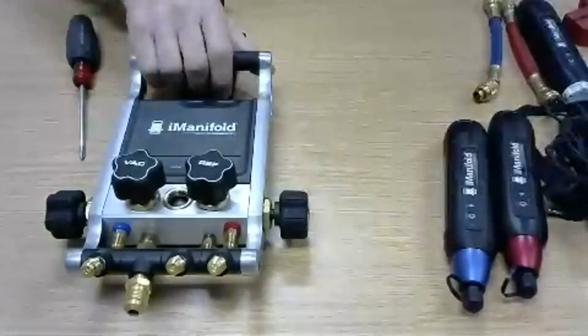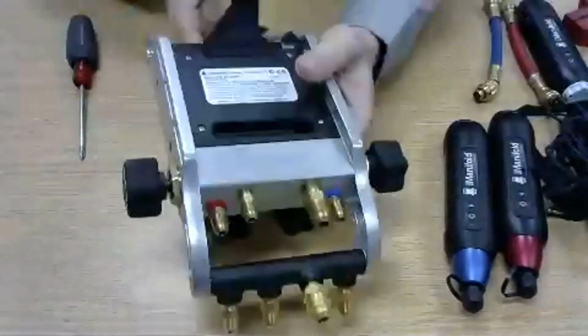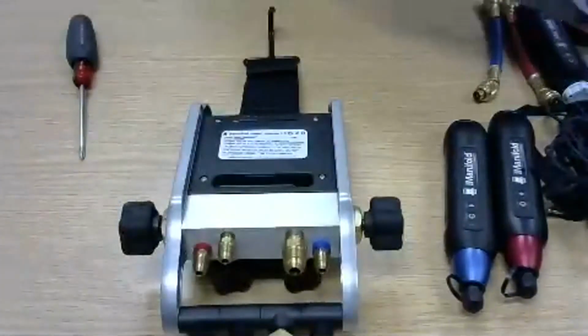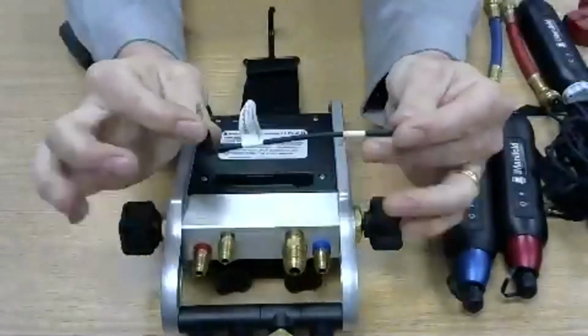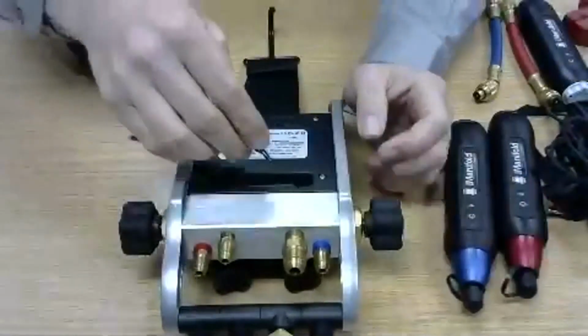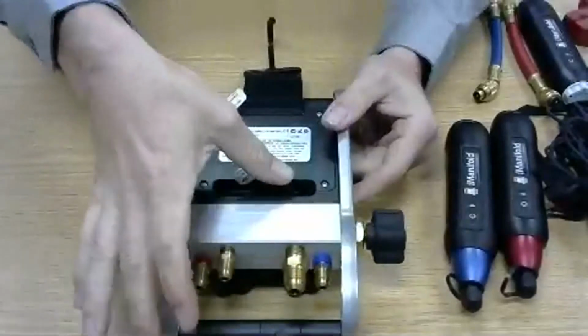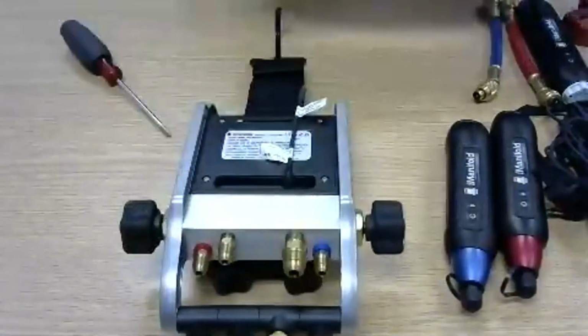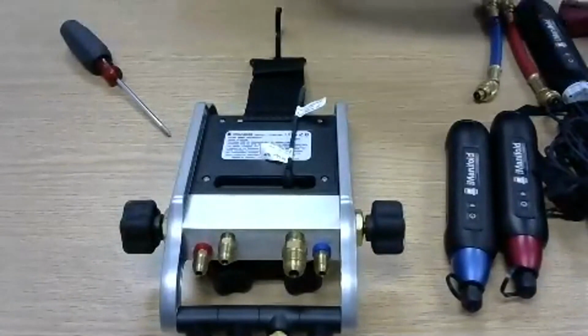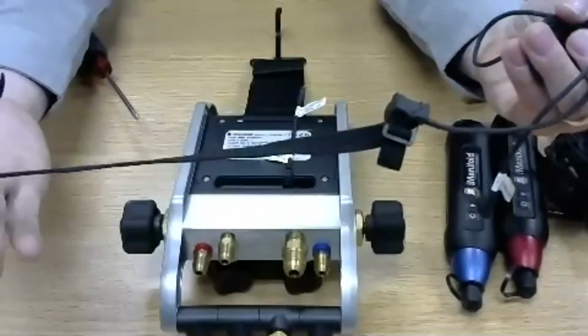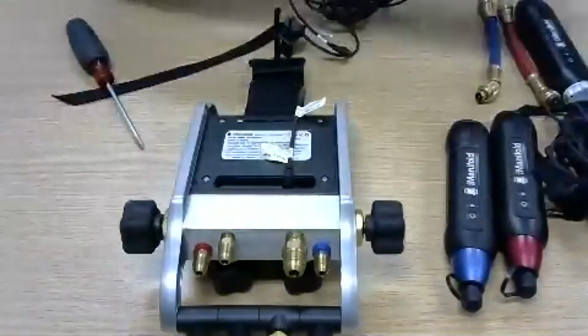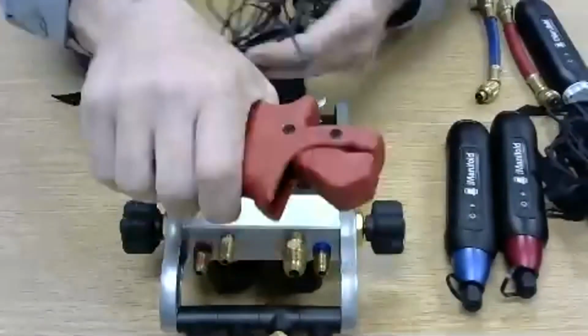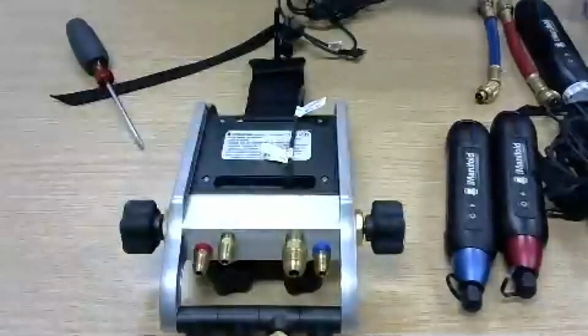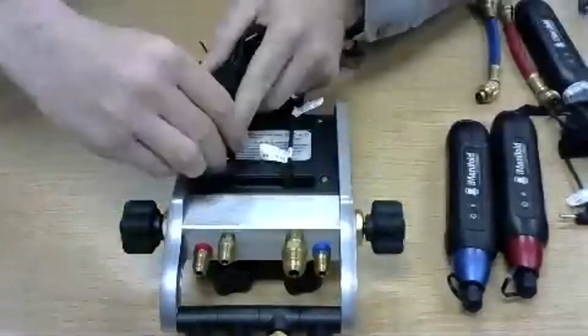As I said before, on the back of the iManifold here, we have our temperature inputs. Today, I'm going to use the little air thermistor, the outdoor air. I'm going to plug it right in there. And we can have either the strap thermistors, like you see here, or the clamp, like you see here. I'm going to use the 2-pipe strap.